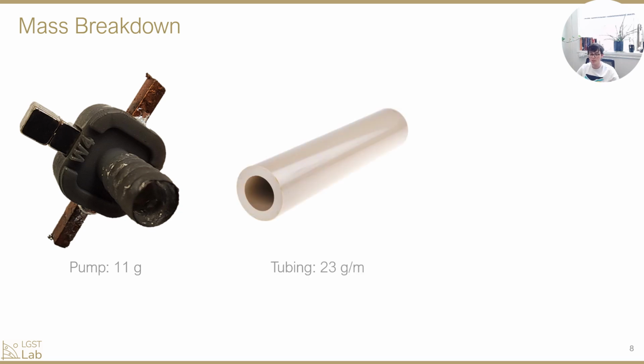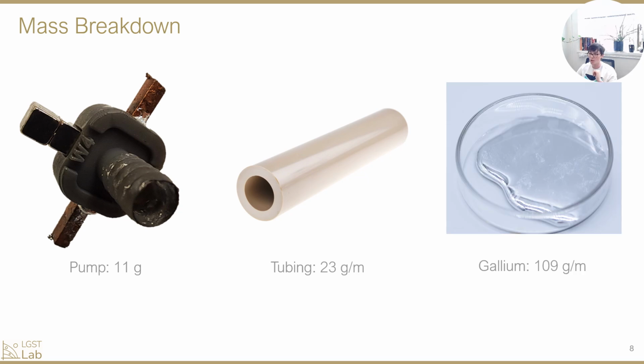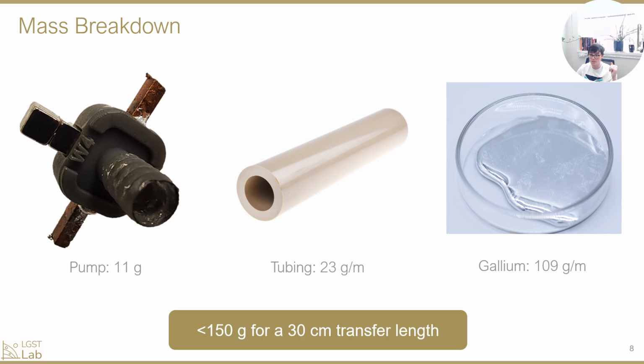For our tubing, if we use PEEK tubing, a flexible plastic we do intend to use, it weighs just 23 grams per meter. Gallium itself is about 100 grams per meter for the tubing diameter we've been using, about 4.76 millimeters. So altogether, we're looking at a system mass of less than 150 grams to transfer heat over a distance of 30 centimeters — that's 30 centimeters there and 30 centimeters back, since there's a loop. Quite light.